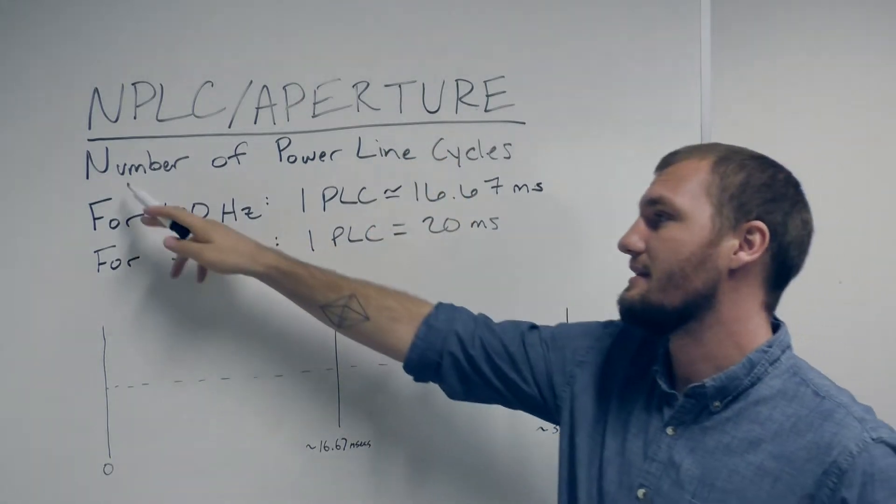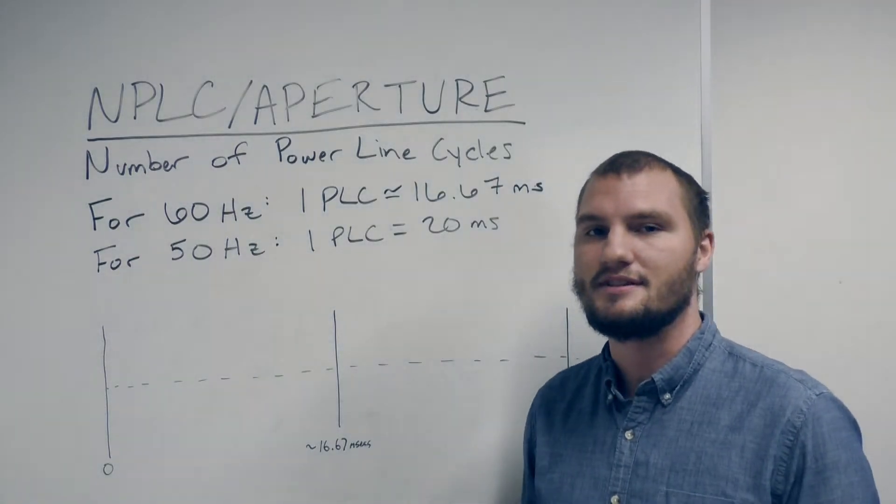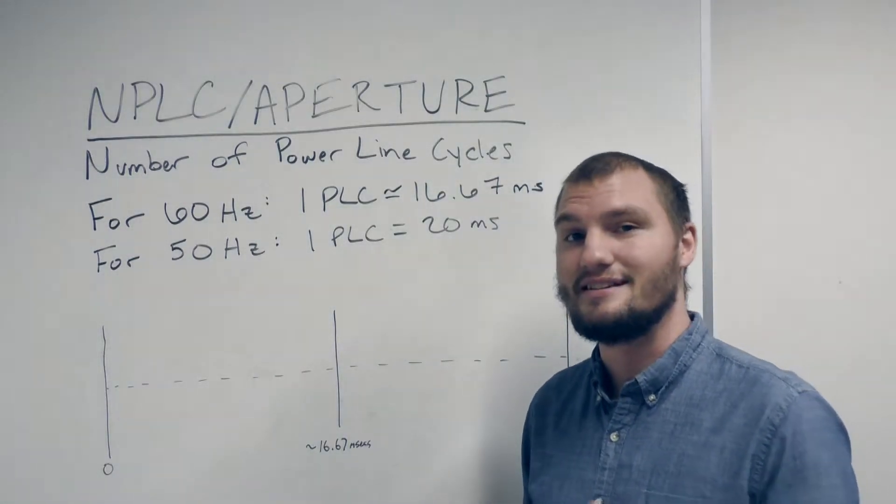This means the number of power line cycles and it describes the amount of time that an input signal is integrated in order to get a single measurement.